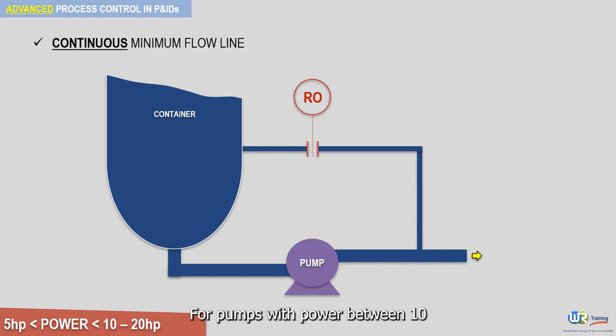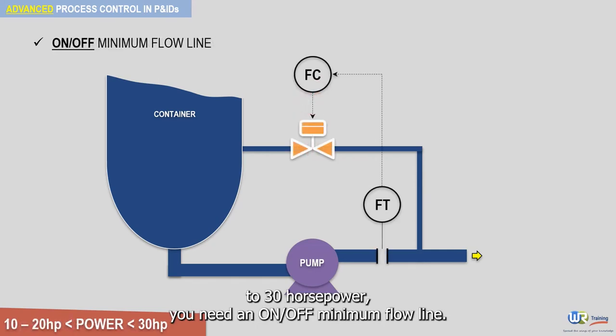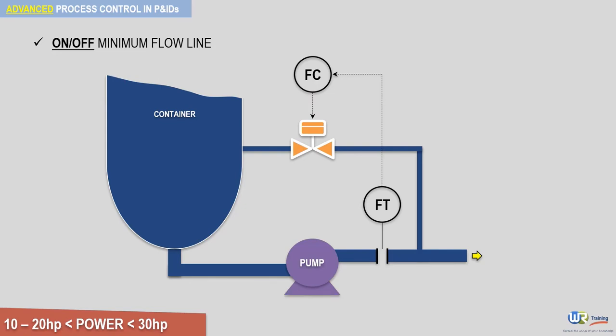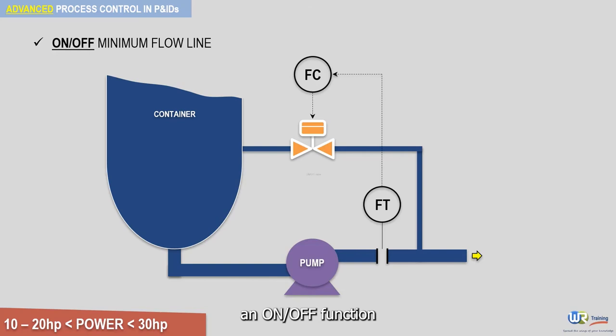For pumps with power between 10 to 30 horsepower, you need an on-off minimum flow line. This is a cheaper option than installing a control valve. In this case, the flow control loop will just provide an on-off function.